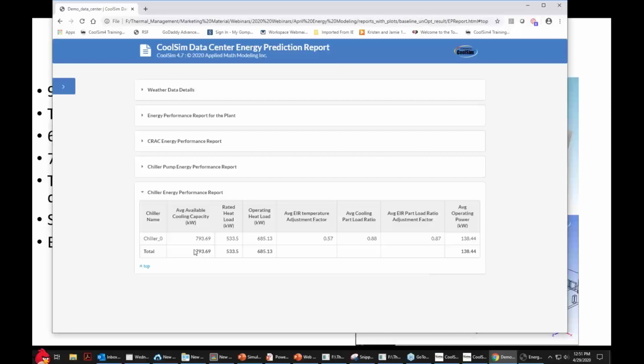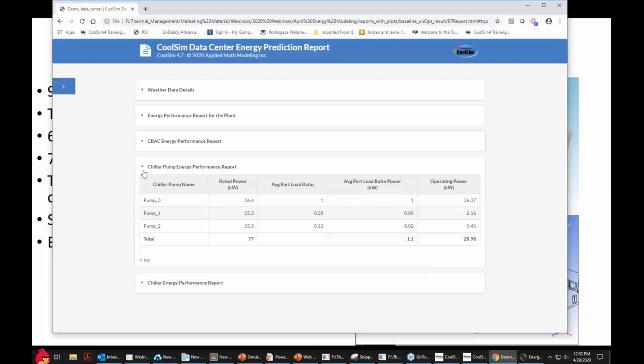One of the questions coming in here, Henry, for you is on the mechanical side, we used a primary secondary pumping system, and the question becomes, do you see variable primary flows? Do you see VFDs being used on the primary side in data centers? Well, I think that they can be used, but you have to maintain a minimum flow to make sure that the chillers will operate efficiently. But the minimum flow gives lots of room for variable speed pumping to have savings versus constant speed pumping for the primary loop. But you'd have to maintain a minimum flow. It can be considerable as well, as we've found, right? Yep.